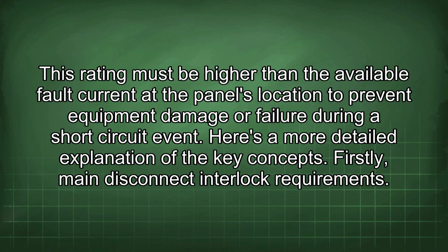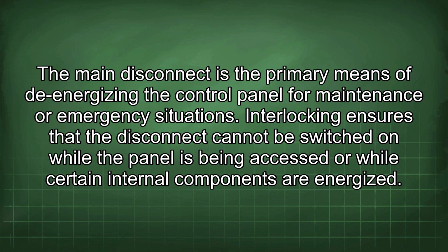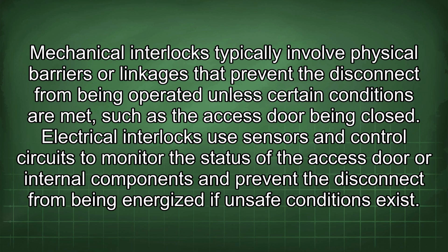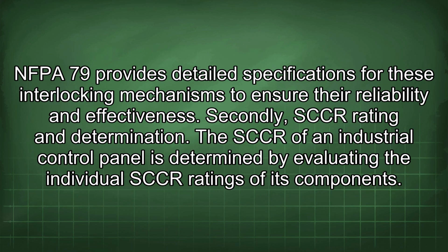Firstly, main disconnect interlock requirements. The main disconnect is the primary means of de-energizing the control panel for maintenance or emergency situations. Interlocking ensures that the disconnect cannot be switched on while the panel is being accessed or while certain internal components are energized. Mechanical interlocks typically involve physical barriers or linkages that prevent the disconnect from being operated unless certain conditions are met, such as the access door being closed. Electrical interlocks use sensors and control circuits to monitor the status of the access door or internal components and prevent the disconnect from being energized if unsafe conditions exist. NFPA 79 provides detailed specifications for these interlocking mechanisms to ensure their reliability and effectiveness.